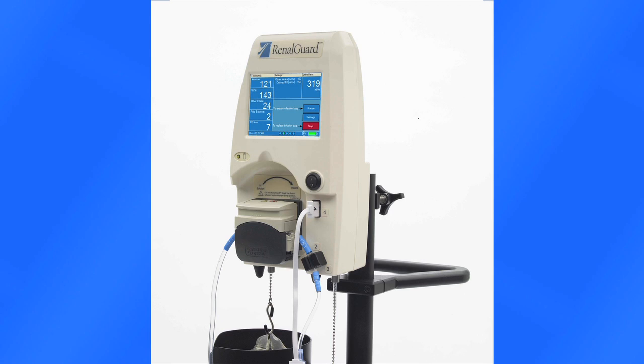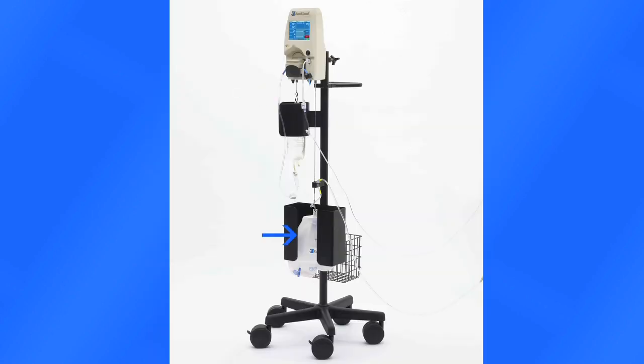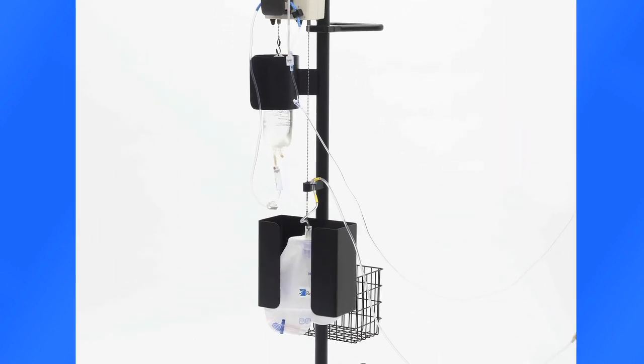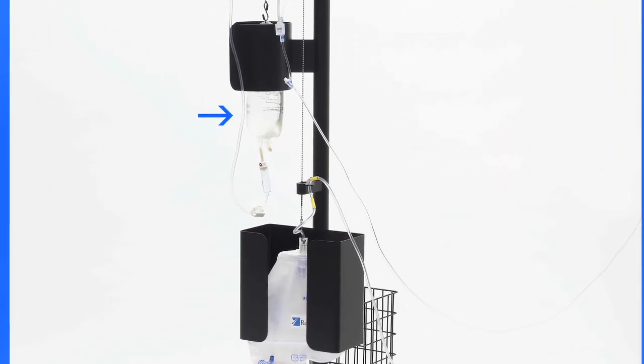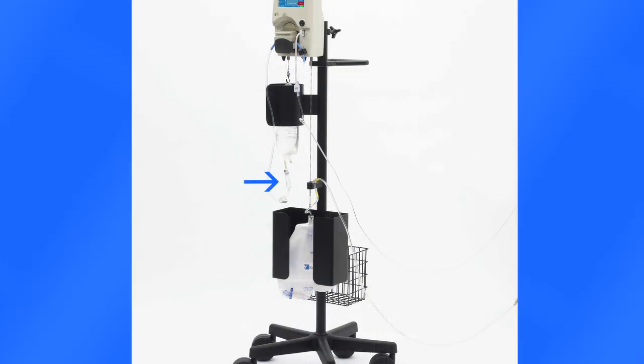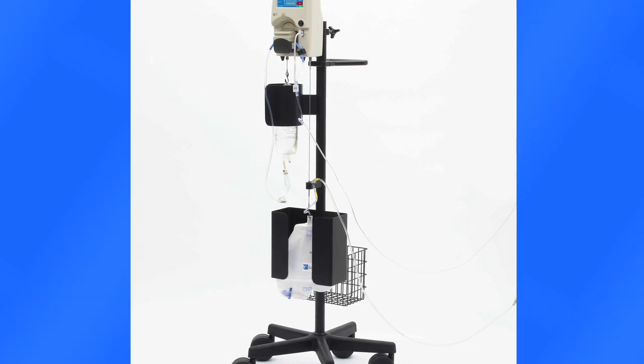Each patient also requires a single-use set, which is made up of an infusion set, a urine collection set, and an extension set. The infusion set connects to the infusion bag. This should be a 1-liter bag of hydration fluid, no more and no less. Plastic bags or plastic bottles can be used, but glass bottles are not acceptable. The infusion set includes a drip chamber, inline pressure sensor, needleless injection port, and standard luer lock adapter.